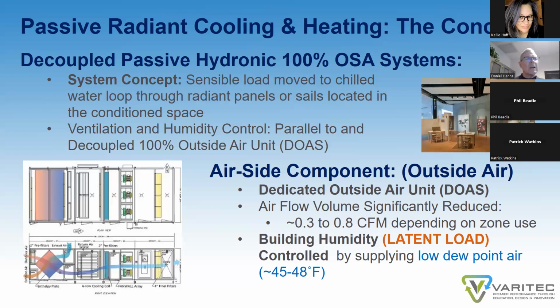Airflow is now designed at about 0.3 to 0.8 CFM per square foot of a building versus 1 CFM to 1.1, 1.2, depending on your geographical location and your peak load conditions. Building humidity, your latent load, is controlled by supplying the outside air at a low enough dew point so that the incoming air absorbs the moisture buildup in the space.